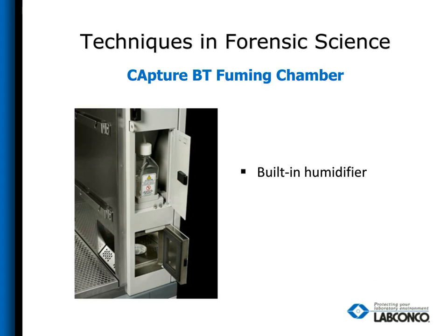A built-in humidifier is included with each Capture BT. This humidifier can be certified with a hygrometer and calibrated. This is an important feature for end users that are working toward performance certifications and standards.